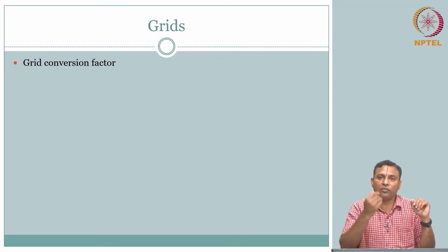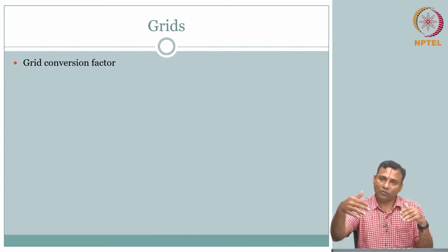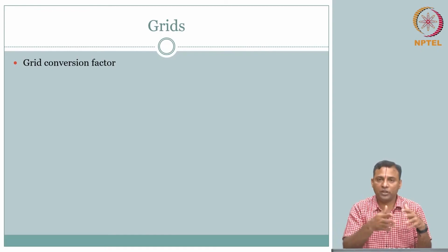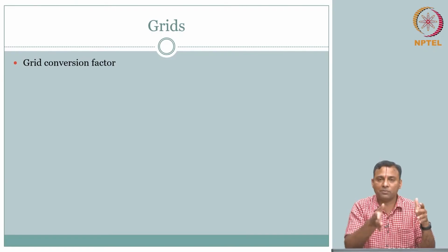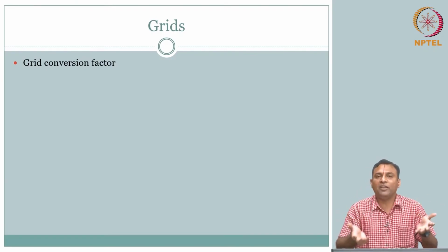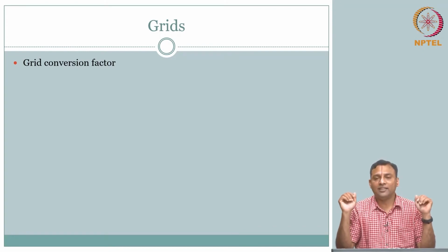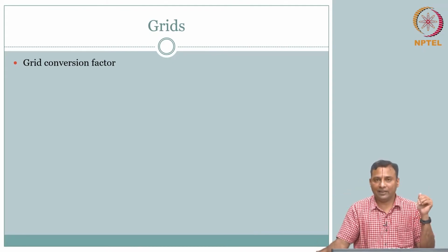If you increase the number of photons for the same schematic, then whatever is Compton scattered will reduce because of the grid, and whatever signal is lost due to the grid placement, you get more photons coming through because you have increased the absolute number of photons. That means your exposure is increased. So, there is always a trade off. Your exposure is increased, but you get better signal to noise ratio because the grids have reduced the scattering.